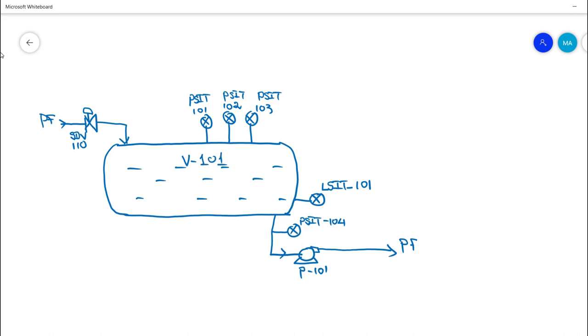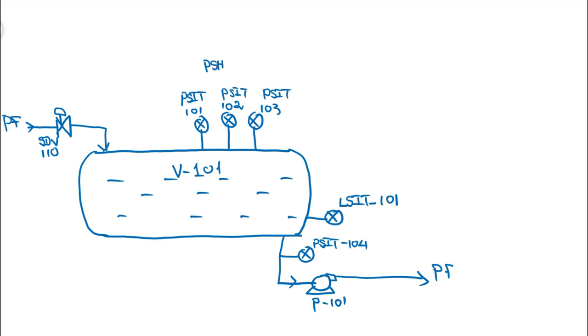The vessel tag number is V-101. For protection, we focus on the ESD tags — DCS tags for alarm and monitoring are excluded from this example. All three pressure transmitters have a high-high trip: when PSHH is initiated by PSIT-101, 102, and 103 on a two-out-of-three voting logic, it trips the main inlet SDV-110.